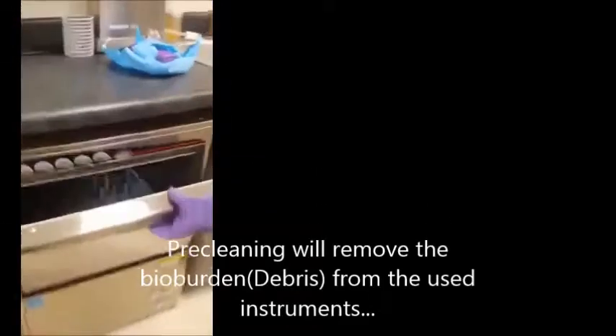For the pre-cleaning procedure, we will use the instrument washer to pre-clean our contaminated instruments. Insert the drain inside the instrument washer at its appropriate place. Load the cassette in the rack and close the washer door. Turn on the instrument washer by pressing the on-off button and wait for the water to fill up. Press the cycle start push button once the water level is complete. Once the cycle is complete, open the washer door and retrieve your cassette.